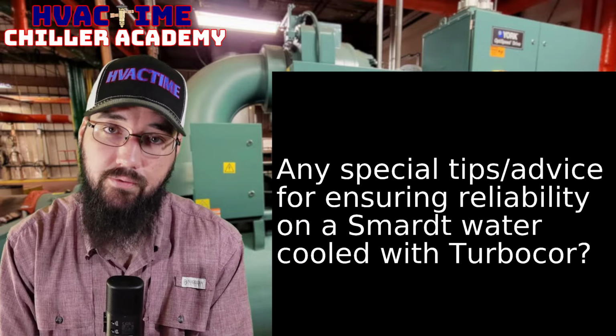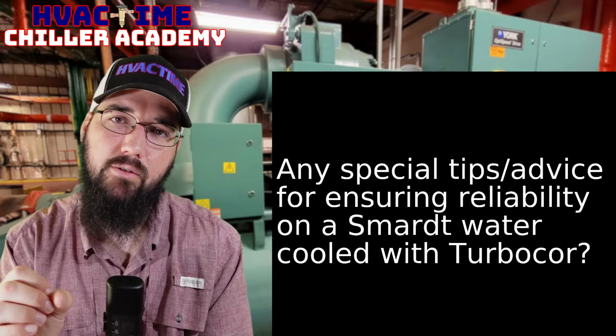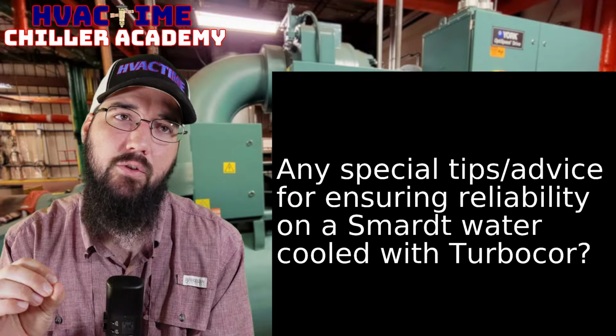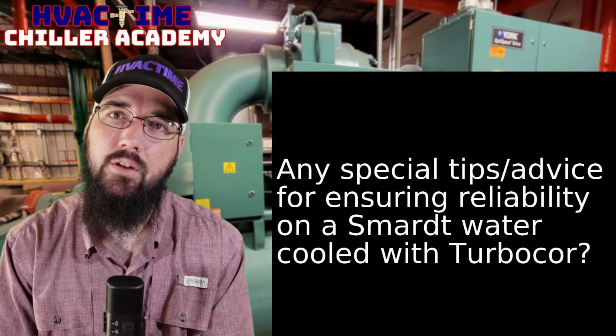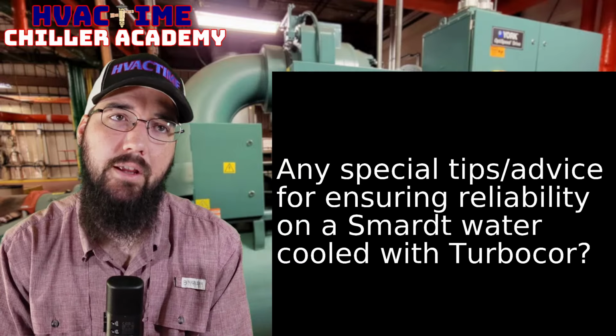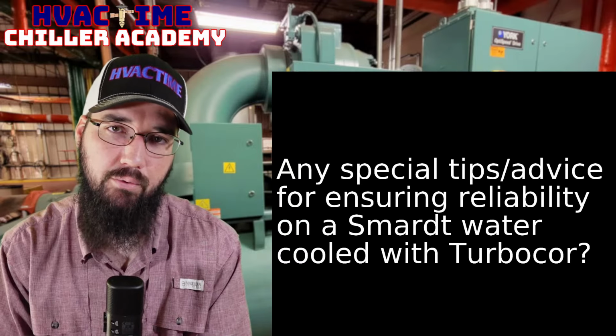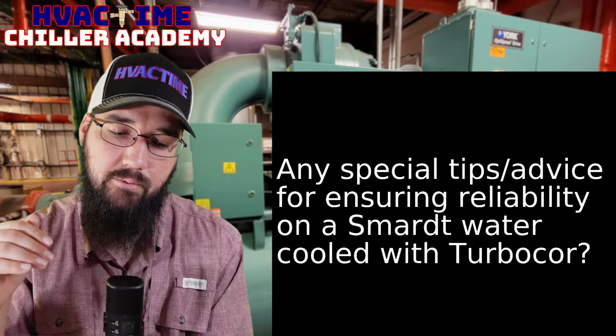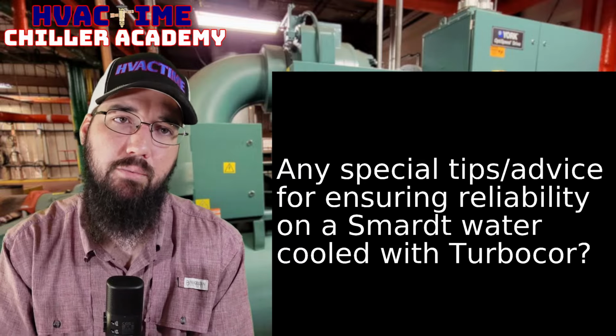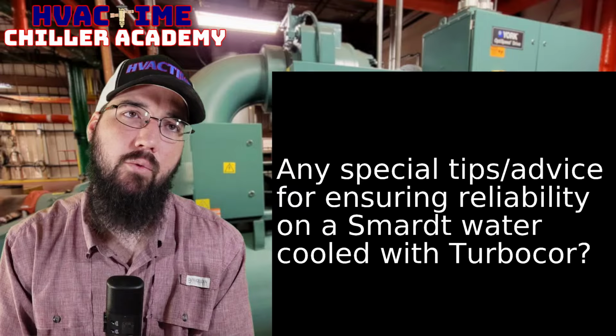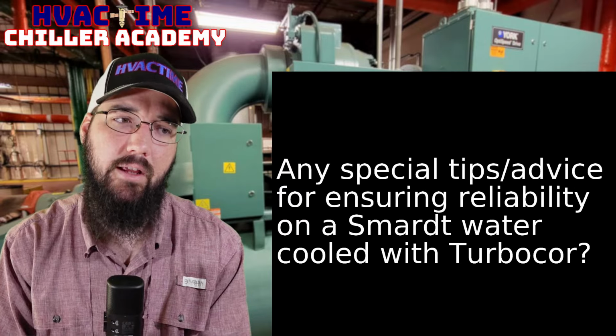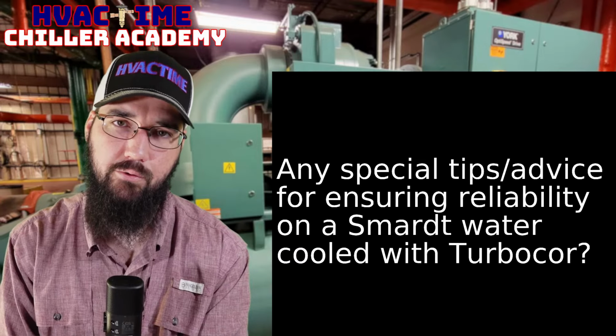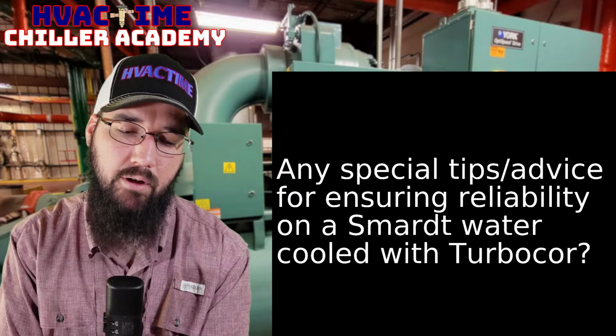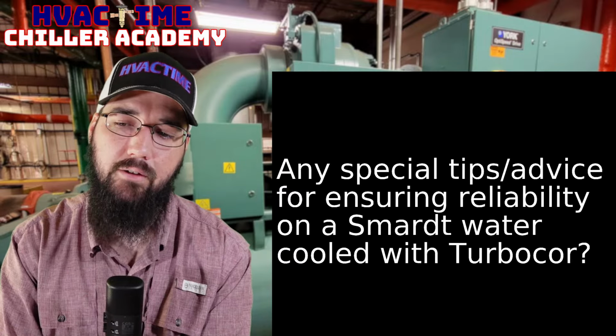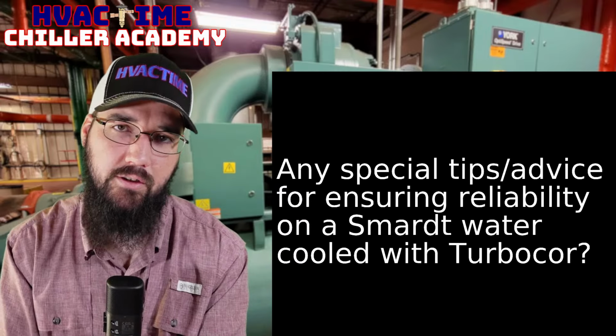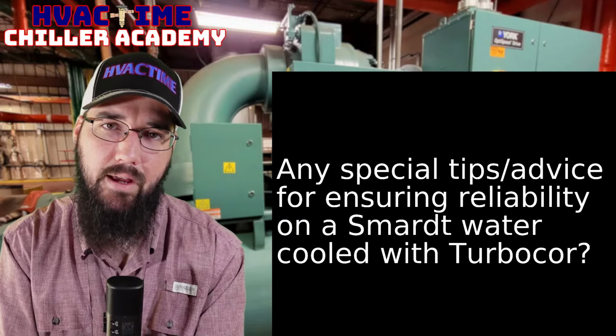So the solution for that is having a liquid pump on the cooling line. I've seen this done two ways. I've seen it done where it would engage the liquid pump all the time, so it was always running if the compressor was calling, always feeding liquid refrigerant from the bottom of the condenser up to the compressor. Or I've seen it done where there was a bypass circuit. If the control system saw that there was an inversion on the loop, it would engage the liquid pump until the inversion corrected. Once we had reached our set points and come out of inversion, it would shut the liquid pump down and run through the bypass, and the bypass had a check valve in it.